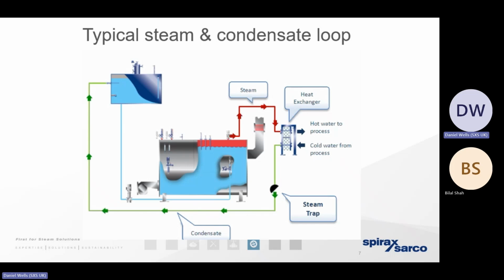So whilst condensate doesn't have a great deal of energy present within it, it's still high temperature hot water, and it's chemically treated hot water as well. So if we can bring that condensate back from the heat exchanger all the way back to the boiler house, that high temperature hot water is giving us a really good head start to produce steam again as efficiently as we possibly can.